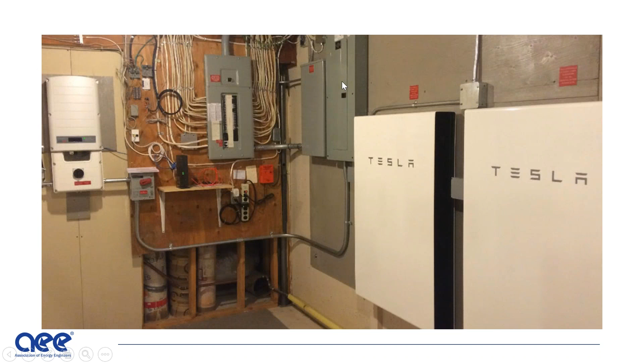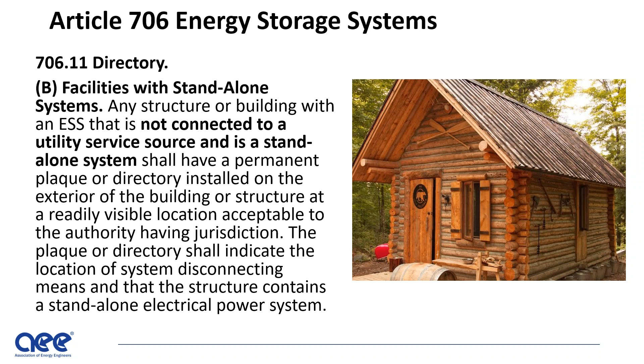Also within Article 706, you have the ability to have a standalone system. If you're out in the middle of nowhere and you have an energy storage system, in this case it's probably going to be something other than just a battery system. But if you happen to be on a structure or building with an energy storage system that's not connected to a utility service source, it is standalone. Another way you would consider a standalone is if you had a PV system and a battery energy storage system, or if you were operating just off a generator and had an energy storage system that works in conjunction with the generator, so you would have power when you had to refuel the generator. Basically, when you talk about standalone systems, it's something that doesn't have any utility connection.